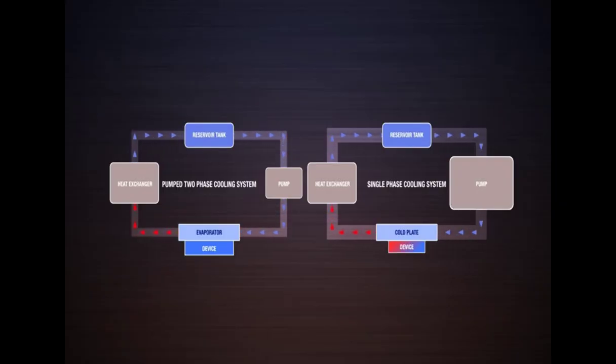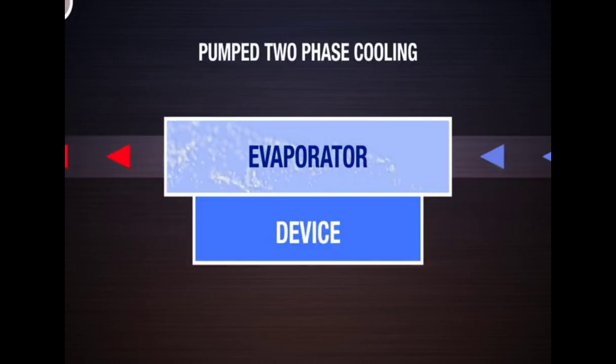Pumped two-phase or evaporative cooling systems use the same basic system-level components as the pump single-phase system. However, pumped two-phase systems typically use refrigerants as the working fluid.